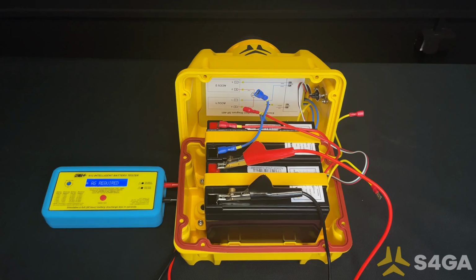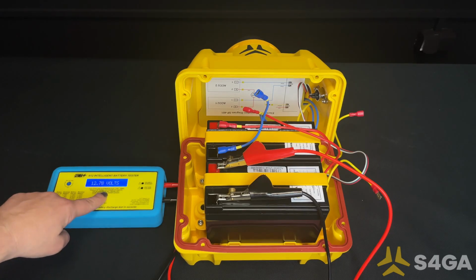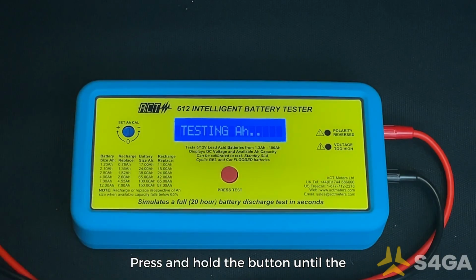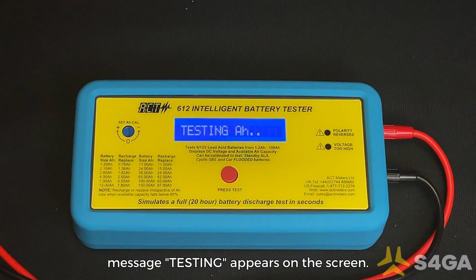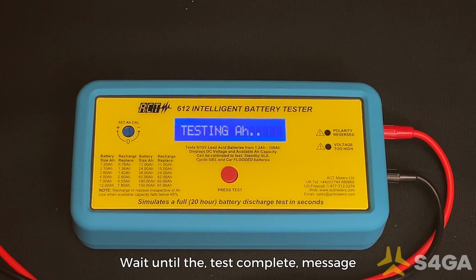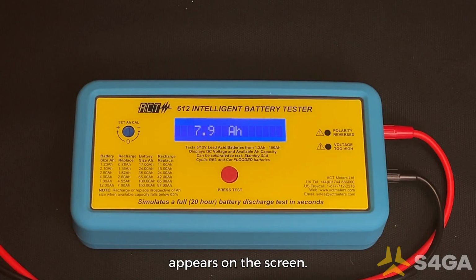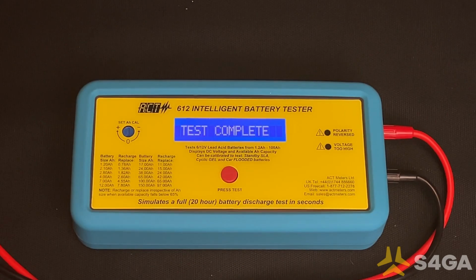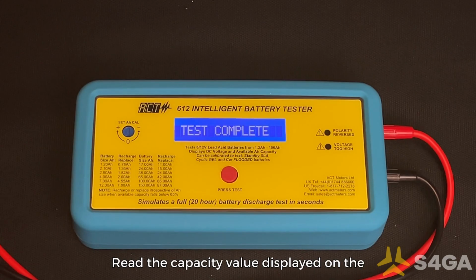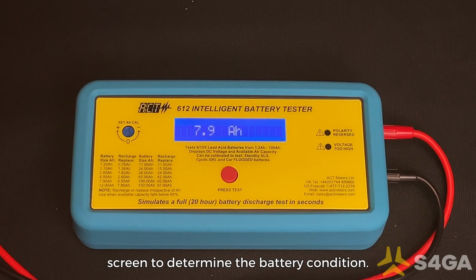To perform a capacity test, press the red button. Press and hold the button until the message "Testing" appears on the screen. Wait until the "Test Complete" message appears on the screen. Read the capacity value displayed on the screen to determine the battery condition.